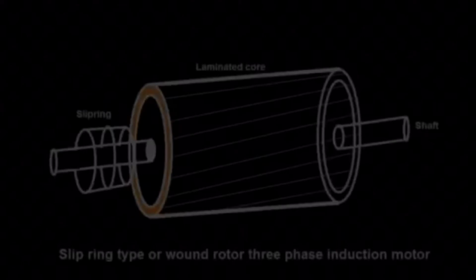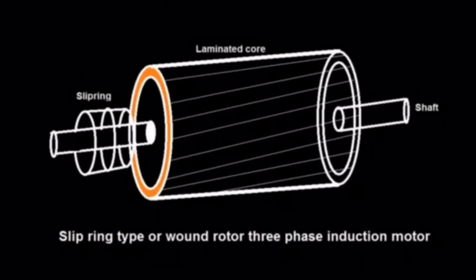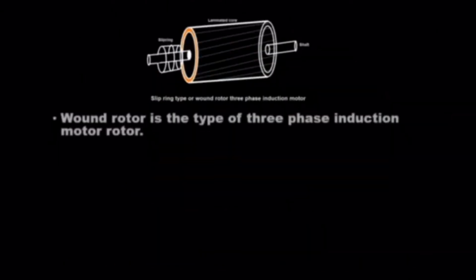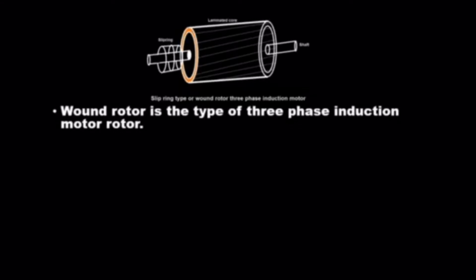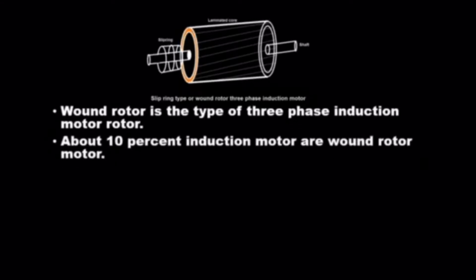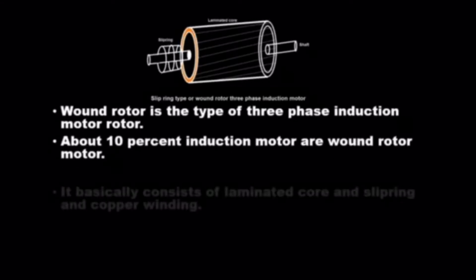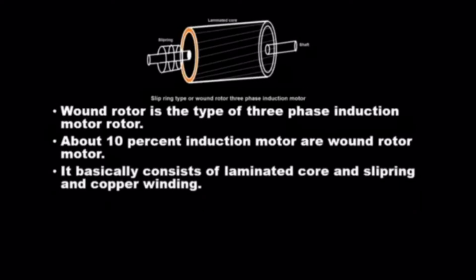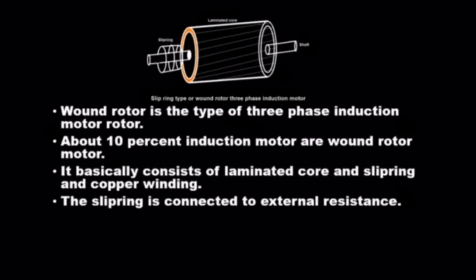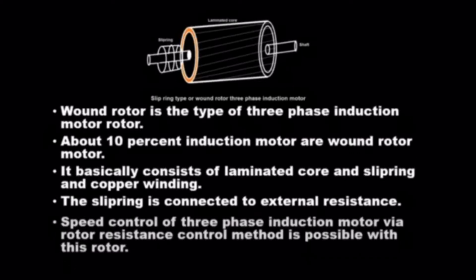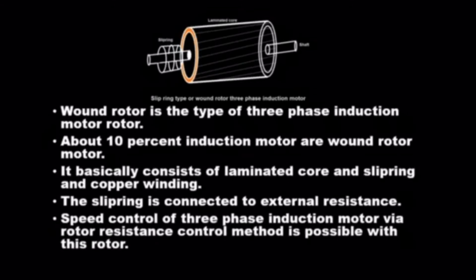Wound rotor. This is a slip ring type or wound rotor three-phase induction motor. About 10% of induction motors are wound rotor motors. It basically consists of a laminated core, slip rings and copper winding. The slip ring is connected to external resistance. Speed control of a three-phase induction motor via the rotor resistance control method is possible with this rotor.